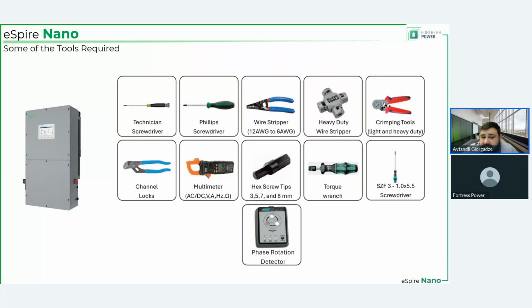Phase rotation detector, though, for people that have not extensively worked with three-phase applications, that could be something new. Now, in single phase or split phase applications, we don't use a phase rotation detector because why would we? It's a single phase split in two. There's no rotation happening between the phases, at least downstream of the meter. But here we have 3 phases, and phase rotation must be correct.